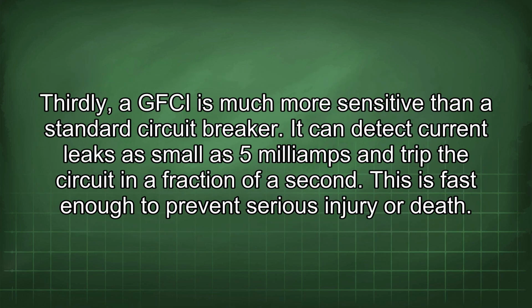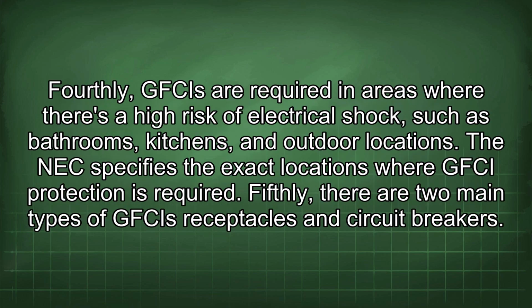Thirdly, a GFCI is much more sensitive than a standard circuit breaker. It can detect current leaks as small as 5 mA and trip the circuit in a fraction of a second. This is fast enough to prevent serious injury or death. Fourthly, GFCIs are required in areas where there is a high risk of electrical shock, such as bathrooms, kitchens, and outdoor locations. The NEC specifies the exact locations where GFCI protection is required.